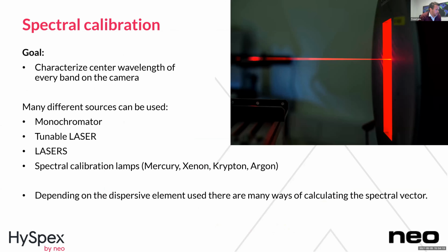Spectral calibration: the goal is to characterize the center wavelength of every band of your camera. Here we illuminate an integrating sphere with many different sources. It can be a monochromator scanning through the whole spectral range, or a tunable laser as well. Those are usually quite expensive, at least if you're covering your whole spectral range. You have different laser sources and spectral calibration lamps like mercury, xenon, krypton, and argon. Depending on your dispersive element, there are many ways of calculating a spectral vector. It's quite different how the spectral sampling looks if you use a prism relative to a grating, for example.